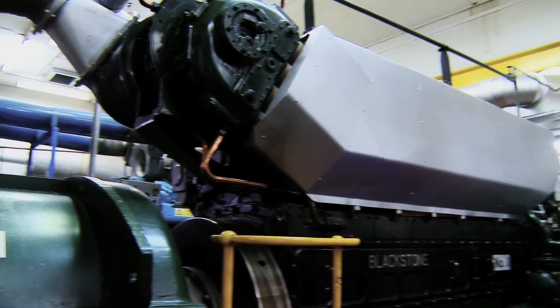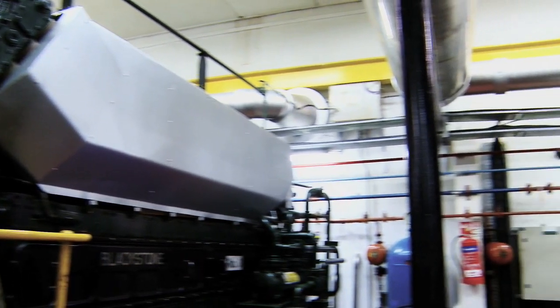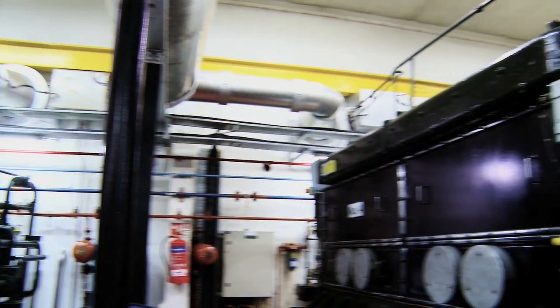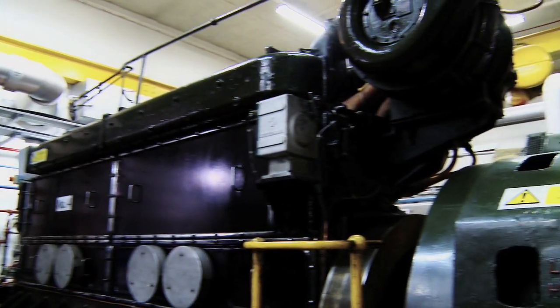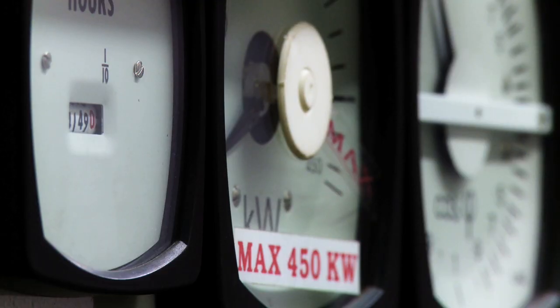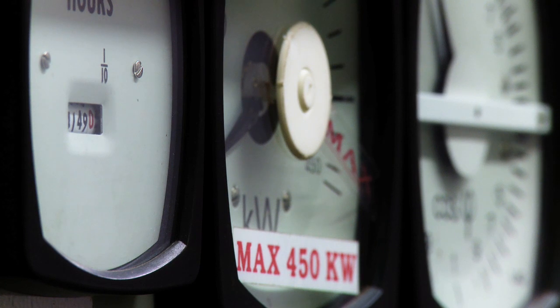If there's an interruption in supply to the islands from the grid, we can supply power via our 7 diesel generators on this site. It's quite simply a case of putting the generators on one at a time, synchronising them onto the bus bars in the switchgear in this switch room. The more capacity we put on the bars, the more supply we can restore to the customers.